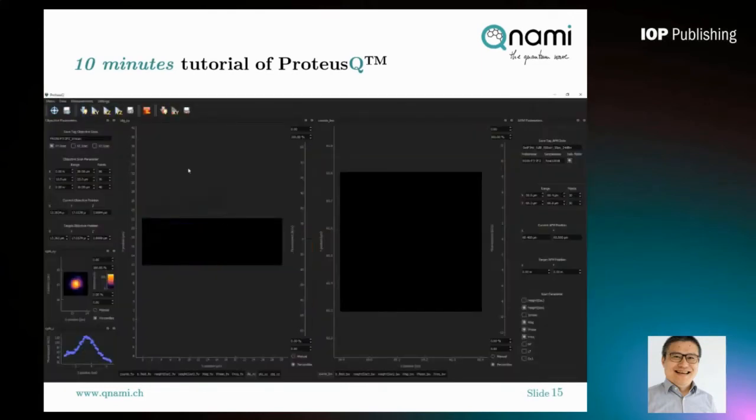We then perform a confocal scan around the cantilever using Qnami's ProteusQ software. In this confocal scan, it is scanned line by line using the top scanner attached to the objective lens. Here you see the bright spot indicating the NV position. The bright features around the edges are mainly due to scattering. We do a one-time click on the NV spot and press the optimization button — the NV position is then automatically optimized.